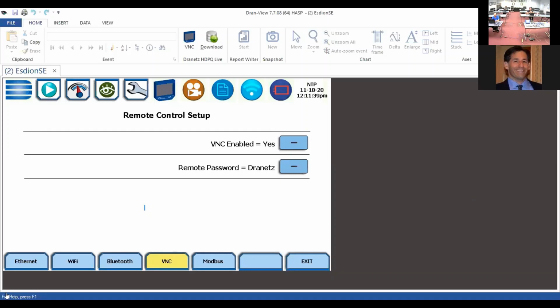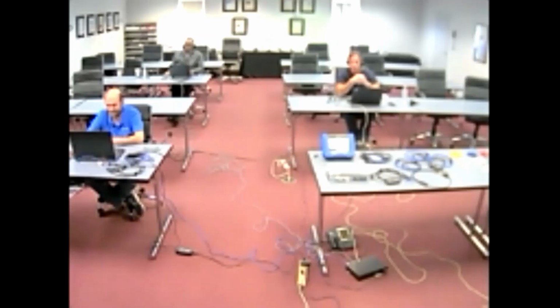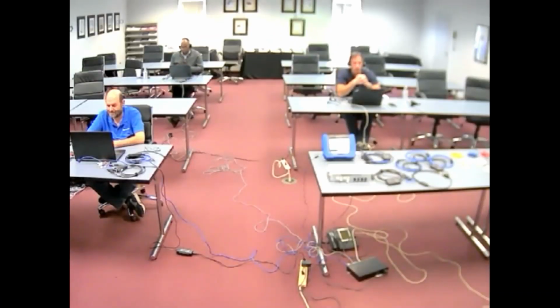Just if I could add, one of the reasons not to use DHCP is that in IT terms it's a leased IP address. Even though you can easily know what the IP address is or was that was assigned by the network, in theory it can change. So if you turn off that instrument and start it back up again, you may have a different IP address.